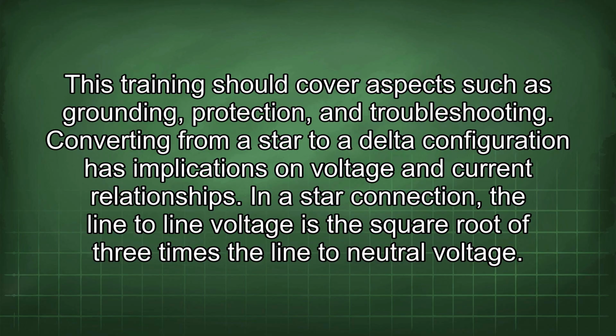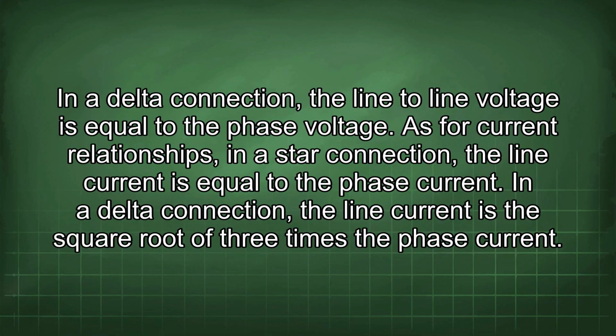Converting from a star to a delta configuration has implications on voltage and current relationships. In a star connection, the line-to-line voltage is the square root of 3 times the line-to-neutral voltage. In a delta connection, the line-to-line voltage is equal to the phase voltage. As for current relationships, in a star connection, the line current is equal to the phase current. In a delta connection, the line current is the square root of 3 times the phase current.